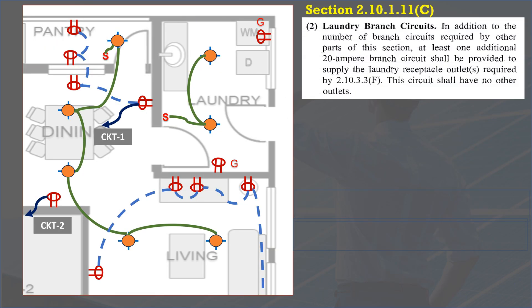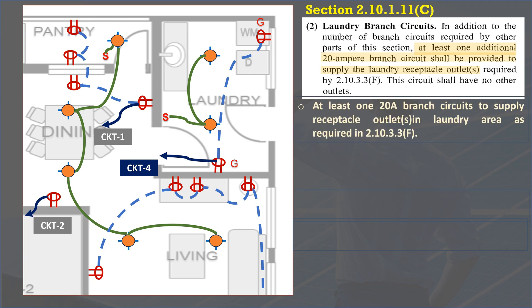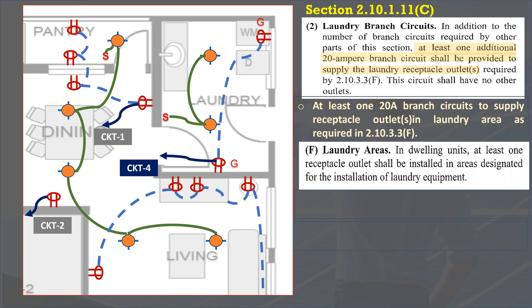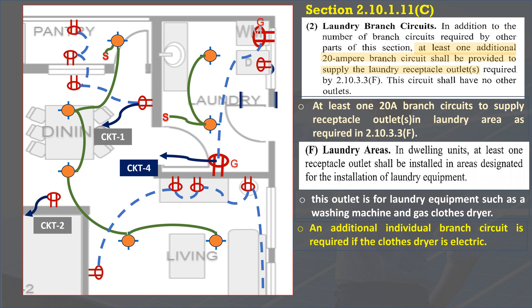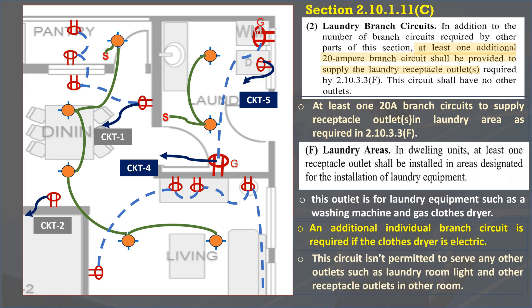Going back to Section 2.10.1.11C, paragraph 2, Laundry Branch Circuits: in addition to the number of branch circuits required by other parts of this section, at least one additional 20A branch circuit shall be provided to supply the laundry receptacle outlet required by 2.10.3.3F. This circuit shall have no other outlets. Laundry areas must have at least one 20A branch circuit for laundry equipment such as a washing machine and gas clothes dryer. An additional individual branch circuit is required if the clothes dryer is electric. This circuit is not permitted to serve other outlets, such as laundry room lights or receptacle outlets in different rooms.